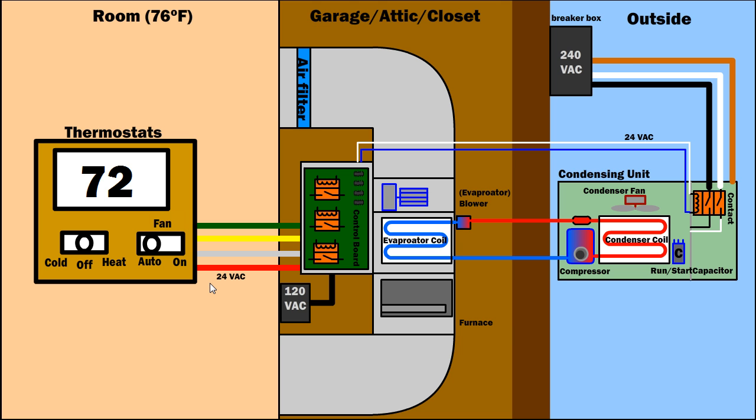Next, you want to test out the thermostat. The very basic way to test it out, the first thing I would always do is let's see if the blower motor works. So in order to do so, you set the thermostat fan on and this forces the blower motor to kick on. So what happens is that 24 volts comes from the circuit board and then it returns back to the green line. And the green line will tell the controller board to turn on, close the relay and turn on the blower. Now you can put your hand at the vents and feel if there's any airflow.